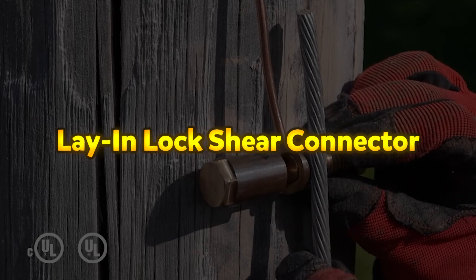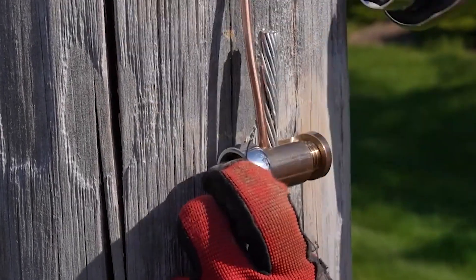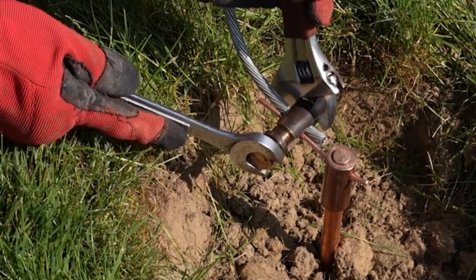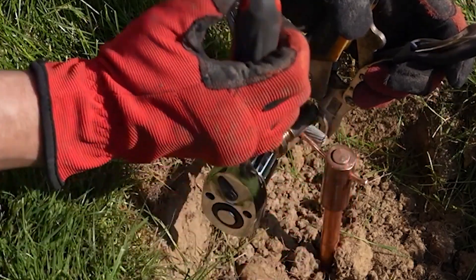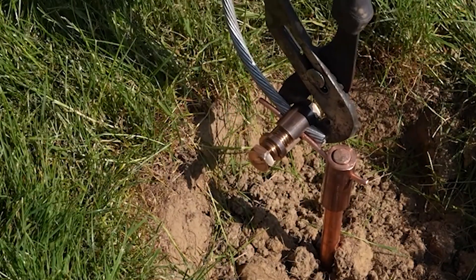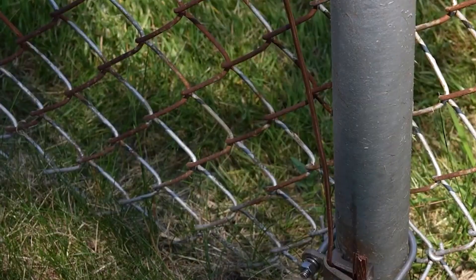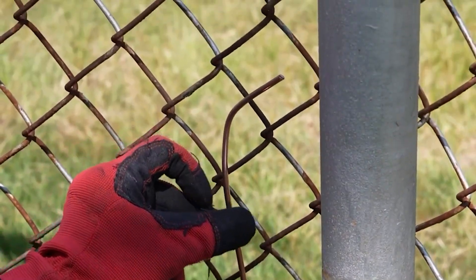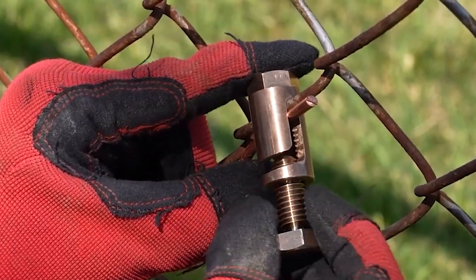Lay-in Lock Shear Connector. The nVent ERICO lay-in lock shear connector is an innovative, tamper-proof solution designed for efficient grounding installations. Its lay-in capability eliminates the need to thread conductors through the connector, making it easy to use while saving time and labor costs. Suitable for both new installations and existing grounding grids, it provides a reliable and durable connection. This low-maintenance connector allows for irreversible parallel connections, ensuring long-term performance. The shear bolt head applies consistent clamping force, while the lay-in feature securely holds conductors in place before tightening.